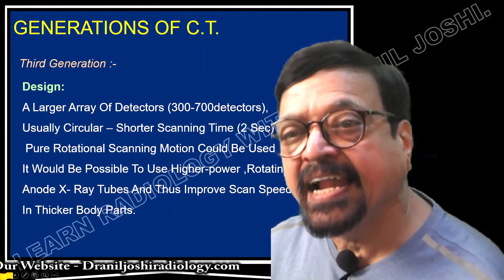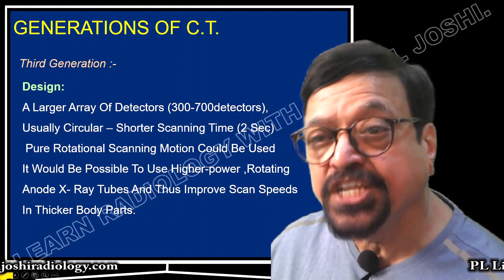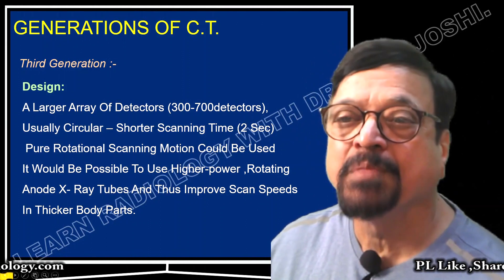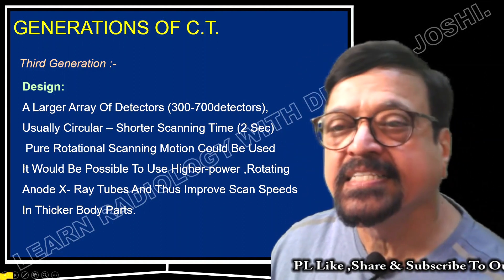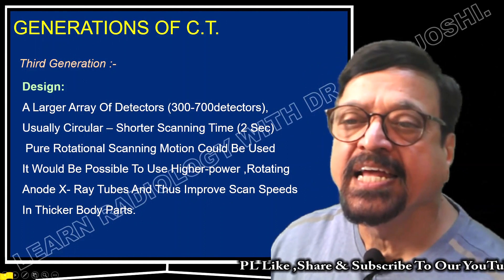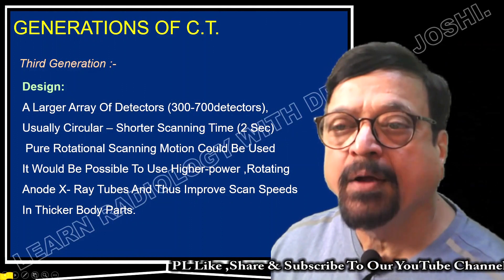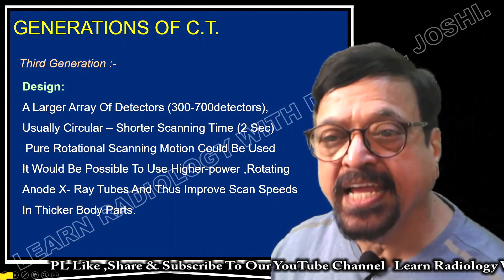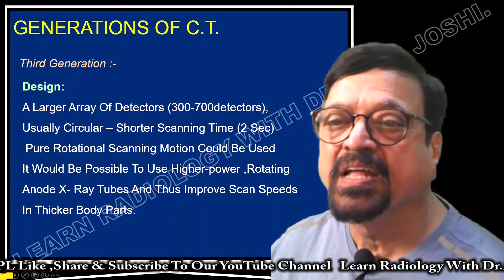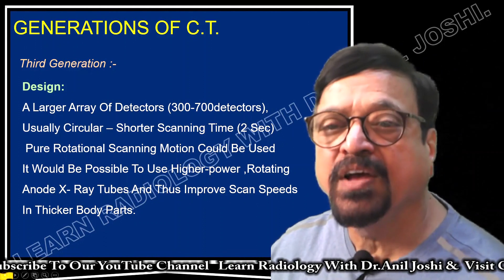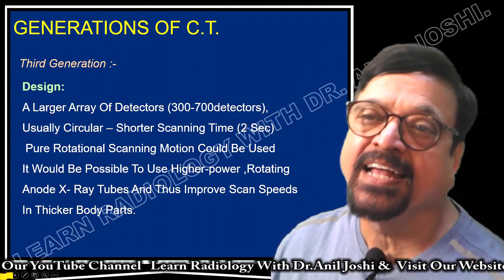The third generation had a larger array of detectors — around 300 to 700 detectors — usually arranged in a circular configuration, giving shorter scanning times because only the tube moves, not the detectors. Pure rotational scanning motion could be used. Higher power rotating anode X-ray tubes could be used to improve scan speed in thicker body parts. High heat dissipation and high rotating anode capability were required for designing a third generation CT scanner.